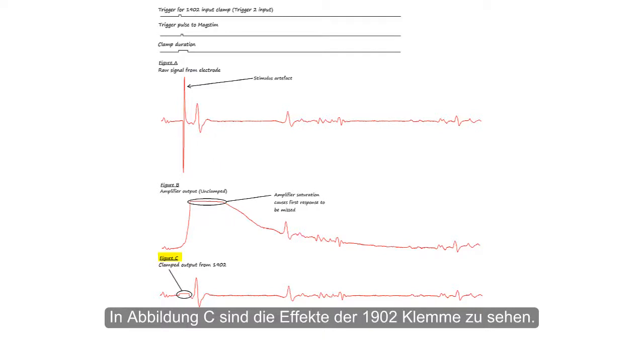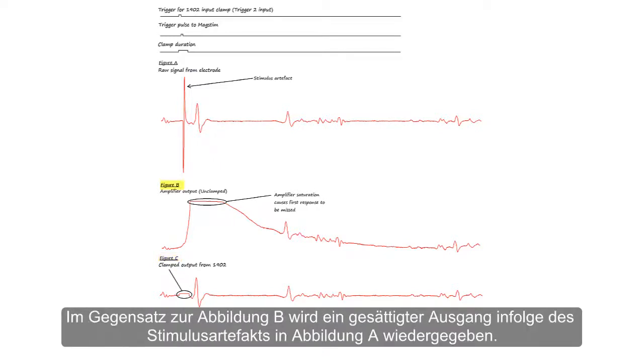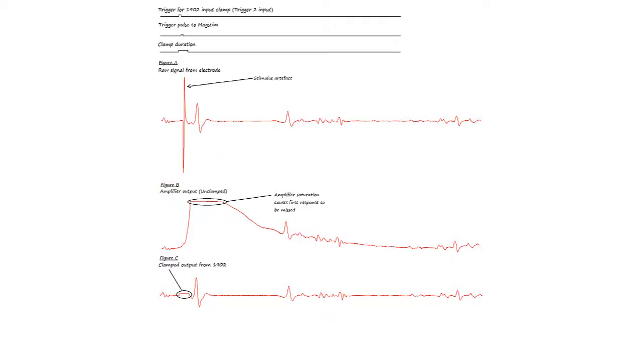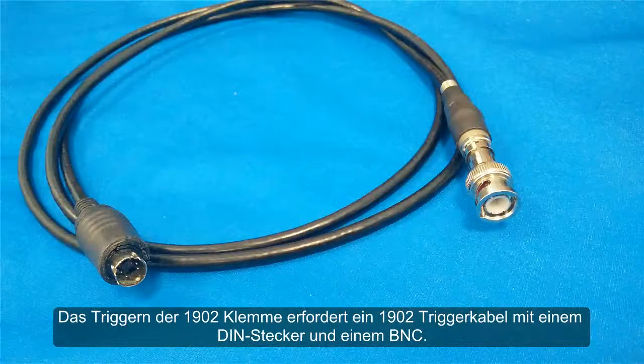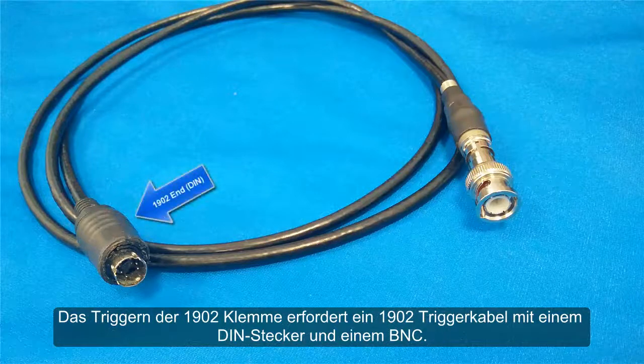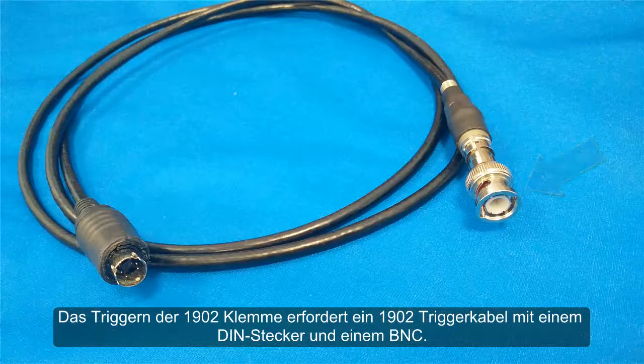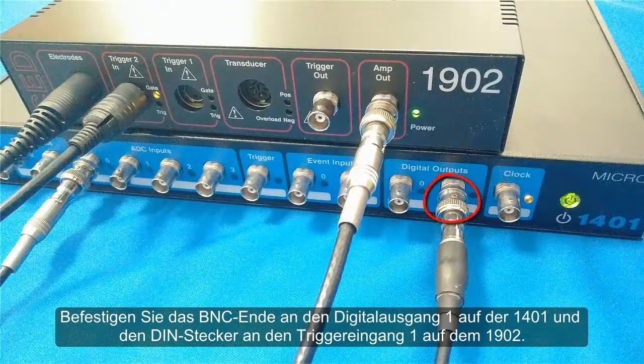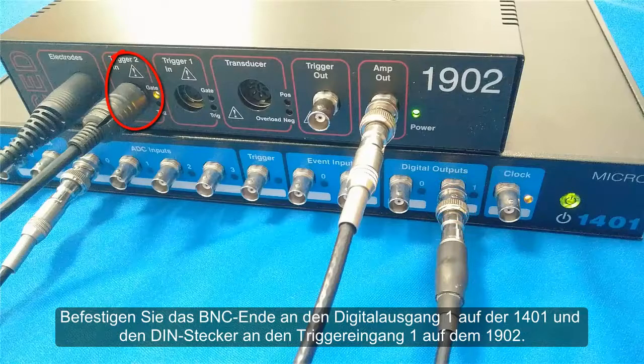In Figure C, you can see the effects of the 1902 clamp, as opposed to Figure B showing a saturated output as a result of the stimulus artifact in Figure A. Triggering the 1902 clamp requires a 1902 trigger cable with a DIN connector and a BNC. Attach the BNC end to Digital Output 1 on the 1401 and the DIN connector to Trigger 2 input on the 1902.